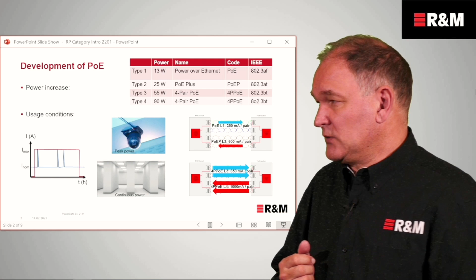Now, not only the amount of power increased over time, also the usage conditions of applications changed a bit. In the early days we mostly had devices that might use some increased power now and then, like a camera that may use extra power to zoom in or move around, but the overall average of the power was quite low. We now see applications emerging that would need the maximum allowed power the whole time, so 24/7. For example, intelligent lights with PoE control would use the complete 90 watts all the time, and that is an additional change of conditions for the cabling.